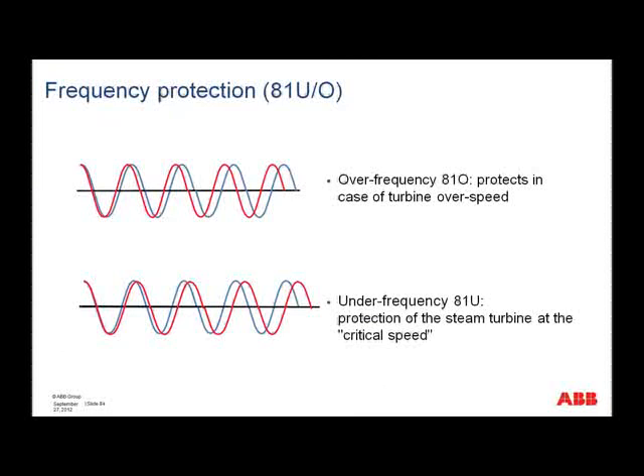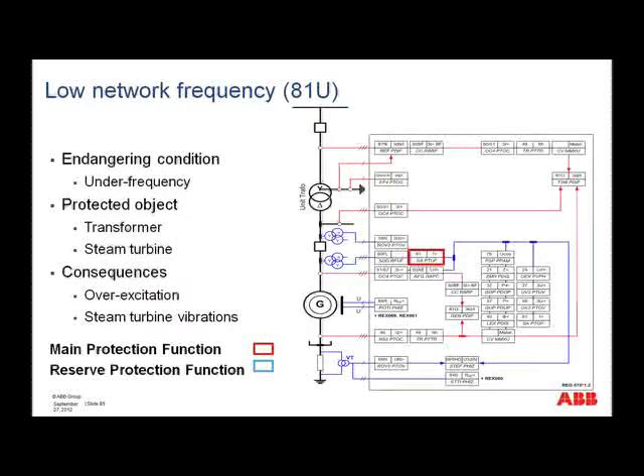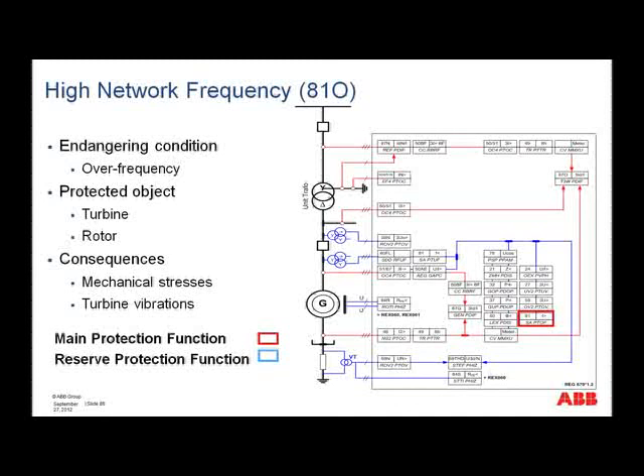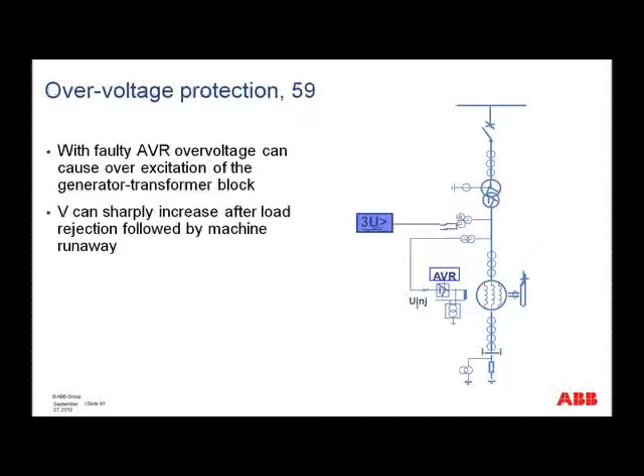Then we have over and under frequency. And here is where we have the under frequency in our protection. Now, one thing to bear in mind, of course, is for the turbine. The turbine is really rated to operate within quite a narrow frequency band. So one of the protected objects here would be the turbine. Also the transformer, because we will talk a little bit later about the overfluxing. And then, of course, if we have overfrequency, this picture here shows where we have the overfrequency protection.